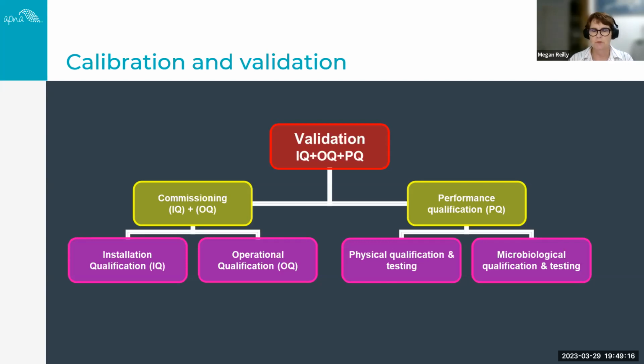So it can actually achieve those minimum conditions through a specified load. So it achieves that minimum sterility assurance to a level of 10 to the power of -6. So your service provider will provide you with a performance qualification report and also a validation test report. And a single page report doesn't meet the requirements. So if you have a service provider that's providing you with a one-page report, you need to really question that. Unfortunately, there's still some cowboys out there, so we need to ensure that our service providers are meeting the requirements of the standard.